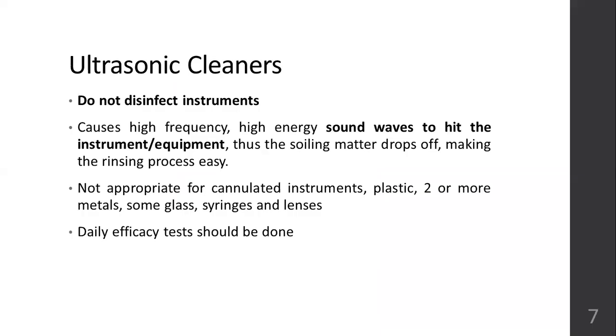Then ultrasonic cleaners. They do not disinfect the instruments at all. High frequency energy or sound waves hit the instrument in such a way that any soiling matter will drop off. Any organic matter will drop off, and that makes the rinsing process easy. Certain areas of the instrument where your hands or a cleaning brush cannot reach, the sound waves can reach, and any soiling matter will drop off. This is not appropriate for cannulated instruments, plastic, two or more metals, some glass, syringes, and lenses. For these kinds of instruments, it is not suited. A daily efficacy test also has to be done.